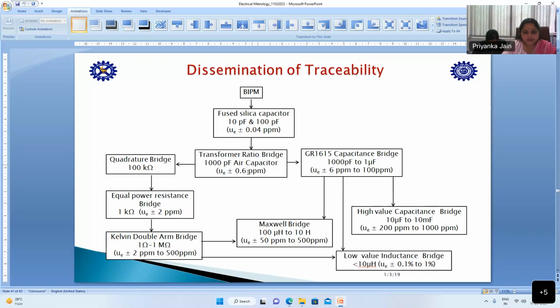And from the quadrature bridge we define the resistance in terms of capacitance. So we have a quadrature bridge also. And then from 100 kilo ohm, we are getting from the quadrature bridge. This 100 kilo ohm defines 1 kilo ohm resistance, which is the reference standard for the calibration of our customers' equipment. So from the 1 kilo ohm standard resistance, we are defining 1 ohm to 1 mega ohm resistance standards. These are our reference standards, which are used to define the customers' calibration standards here.